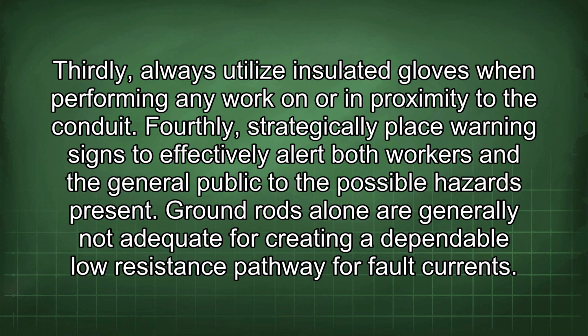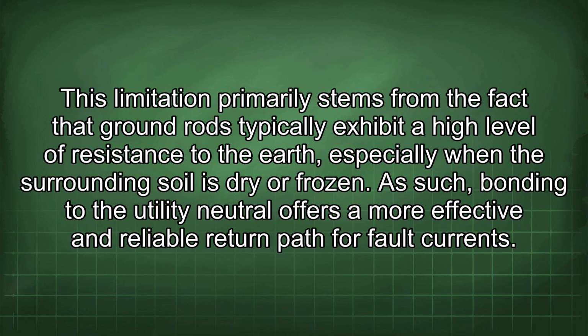Ground rods alone are generally not adequate for creating a dependable low-resistance pathway for fault currents. This limitation primarily stems from the fact that ground rods typically exhibit a high level of resistance to the earth, especially when the surrounding soil is dry or frozen. As such, bonding to the utility neutral offers a more effective and reliable return path for fault currents.